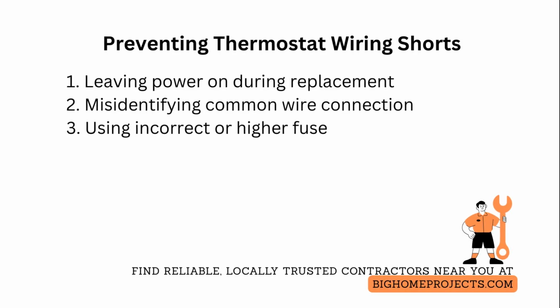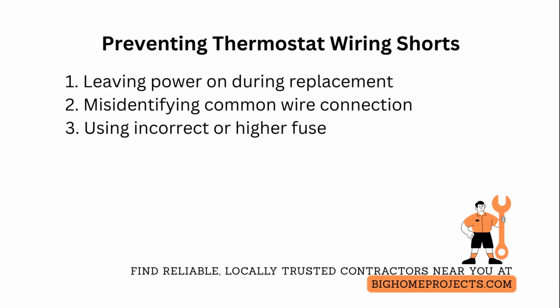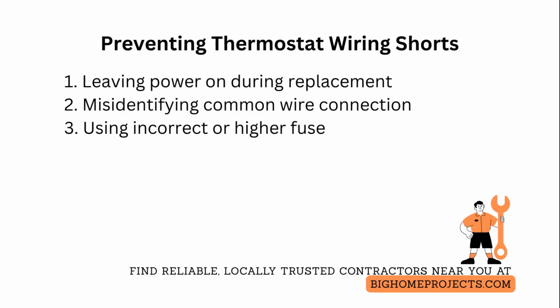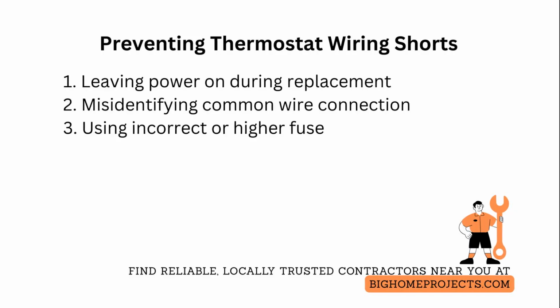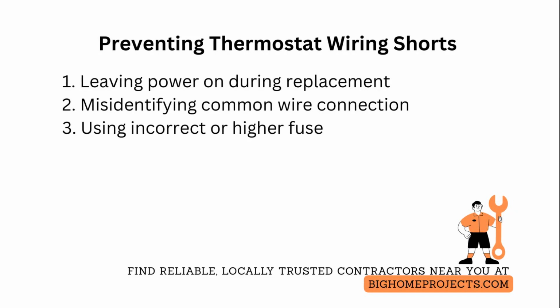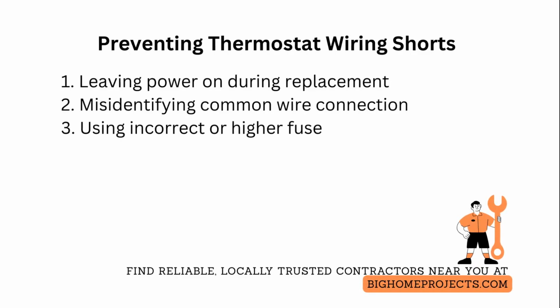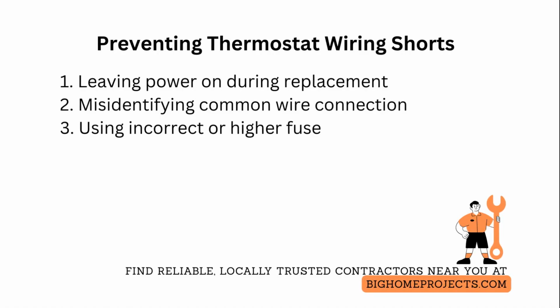One of the other frequent errors is leaving exposed wire strands that short between common and red during reconnection. Correct this by using heat shrink, insulated ferrules, or tape on conductor tips, and keeping wires separated. One of the remaining mistakes is replacing a blown fuse with the wrong rating, which risks damage or nuisance trips.